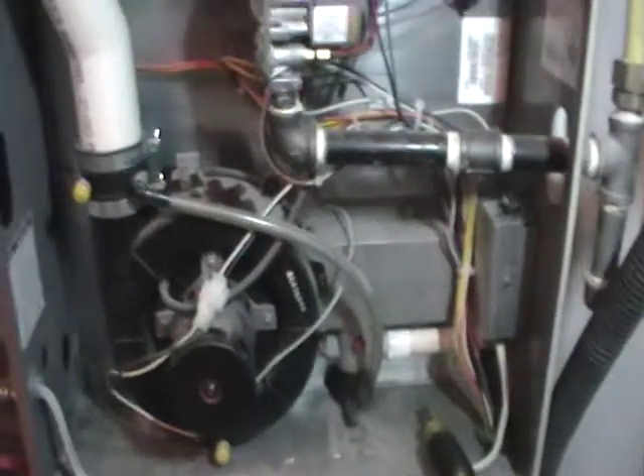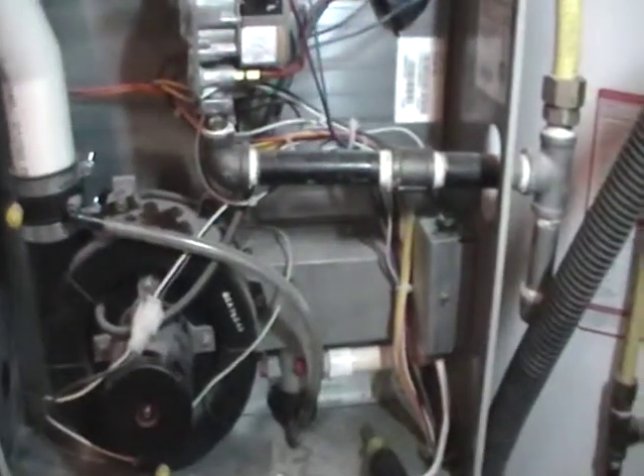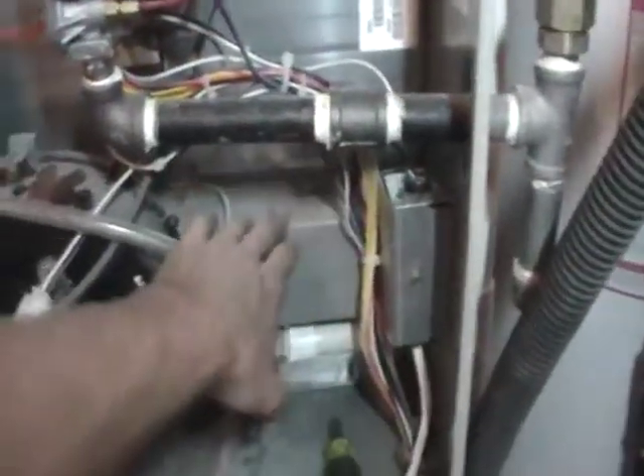And then in a high efficiency furnace, you want to just take a look at the condensate pump if you do have one, or in this case the condensate would just run off to the floor drain. Now, a high efficiency furnace gets the high efficiency from getting the flue gases to condense, which is on the secondary heat exchanger on the bottom. You can see here it just drains off to the floor drain, but if you do have a condensate pump, you can always pour some water in there and just make sure that the pump cycles properly.